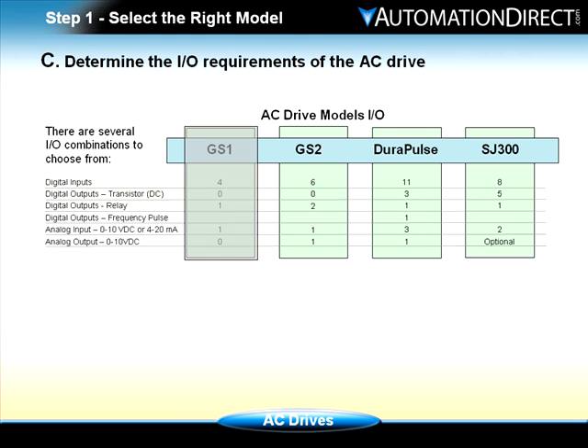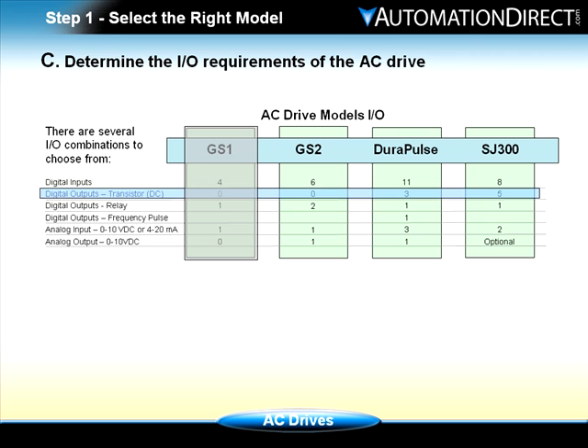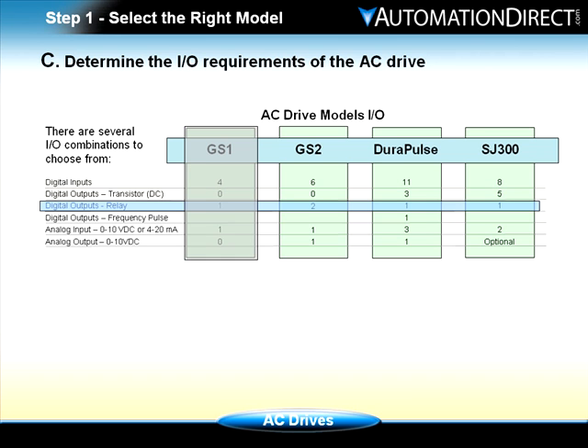Let's look at the I/O configurations of the different modules. Digital inputs are used to interface an AC drive with devices such as push buttons, selector switches, and PLC digital output signals. These signals are typically used for functions such as start/stop, forward/reverse, external fault, and fault reset. Digital outputs are used to connect the AC drive to pilot lights, alarms, auxiliary relays, solenoids, and PLC digital input signals. Transistor outputs are rated for DC voltages, whereas relay outputs work with both AC and DC voltages.